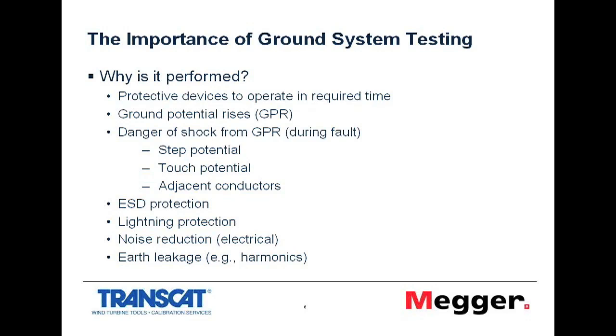Also, in terms of fault conditions, ground potential rises are another hazard. If the connection to ground isn't low enough, then you can get a step potential across a piece of ground as the current flows through it. You can get a touch potential on things like metal fences or anything which is connected to the ground system which might end up with a potential across it due to a poor connection to ground. And also adjacent conductors can have a relative voltage between them.